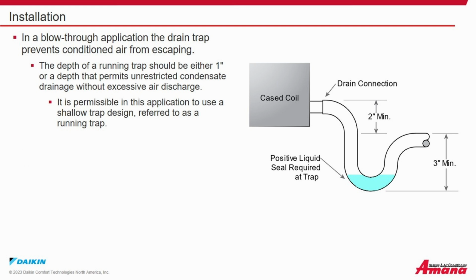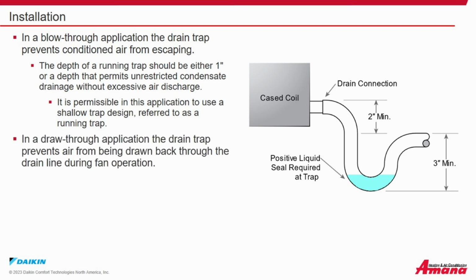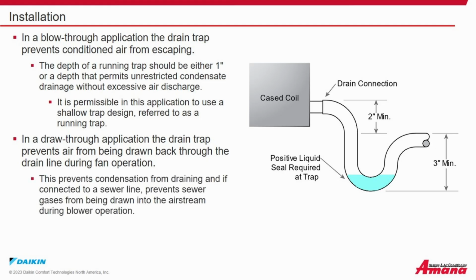trap. In a draw-through application, such as a coil being mounted to the inlet side of an air handler, the drain trap prevents air from being drawn back through the drain lines during fan operation. This prevents condensation from draining, and if the drain line is connected to a sewer line, it prevents sewer gases from being drawn into the airstream during blower operation.